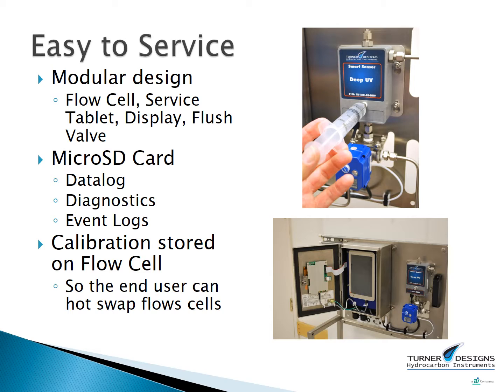Local operators will appreciate the diagnostics, data log, and event log stored inside the TD120. They'll also appreciate the fact that there is a micro SD card with a duplicate data storage. When troubleshooting is needed, the micro SD card can be removed from the TD120. The text files for this troubleshooting are emailed to a local service engineer. When the micro SD card is reinserted, the data log, event log, and diagnostics will be synchronized with internal data.